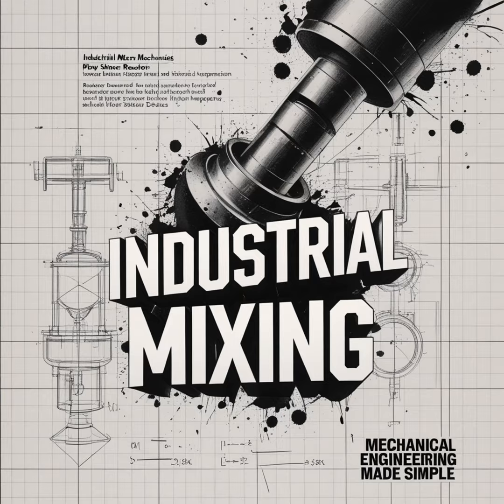And the complexity of these fluids leads to a major design challenge, especially in large fermentations or polymer processing, something called cavern formation. Cavern formation is the classic sign that you have insufficient power input in a highly viscous, shear thinning, or yield stress fluid, like in xanthan gum fermentations. What does that look like?